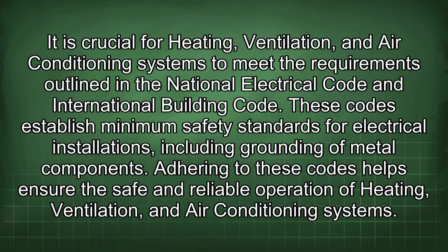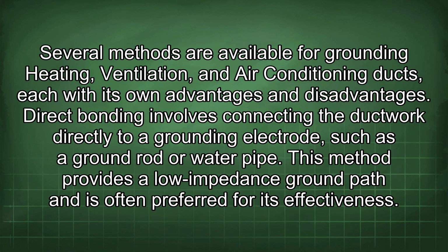It is crucial for heating, ventilation, and air conditioning systems to meet the requirements outlined in the National Electrical Code and International Building Code. These codes establish minimum safety standards for electrical installations, including grounding of metal components. Adhering to these codes helps ensure the safe and reliable operation of heating, ventilation, and air conditioning systems. Several methods are available for grounding heating, ventilation, and air conditioning ducts, each with its own advantages and disadvantages. Direct bonding involves connecting the ductwork directly to a grounding electrode, such as a ground rod or water pipe. This method provides a low impedance ground path and is often preferred for its effectiveness.